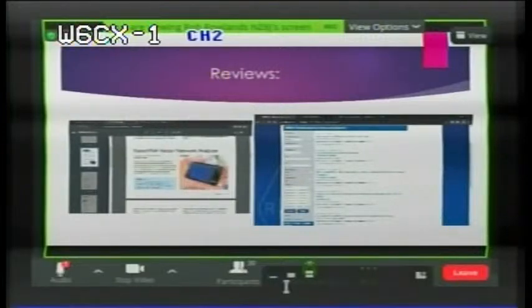Can I answer the second one first? The calibration isn't like you'd expect for a multimeter or another instrument, where you're dealing with systemic deterioration of the product. The calibration is actually because every time you connect the device up, you're connecting to different things, and you're calibrating out the physical extensions of connectors rather than calibrating the measurement system. A device like this doesn't have calibration like a multimeter or some other device.